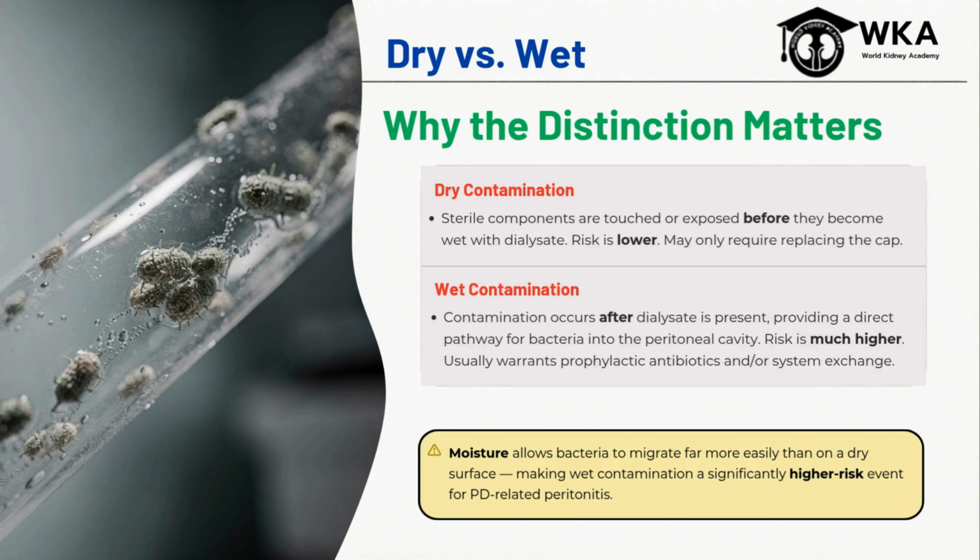The take home message is this: don't focus on whether someone briefly touched the connector, focus on when they touched it. Was the system still dry, or had dialysate already created a fluid pathway? That single difference changes the biology, changes the risk of bacterial migration, and ultimately changes your management.